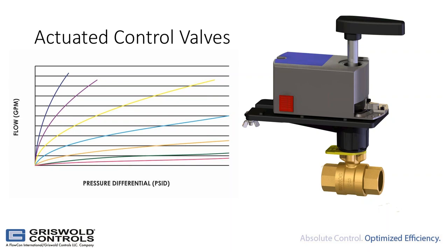Simply put, an actuated valve controls how much flow goes to a coil or terminal unit. Each coil has a control valve with some kind of electronic actuator — typically nowadays it's an electronic actuator on the valve with a motor that controls the valve position. The actuator receives a signal from the thermostat in the room or from the control system, which simply tells the valve to rotate to a more open or more closed position.